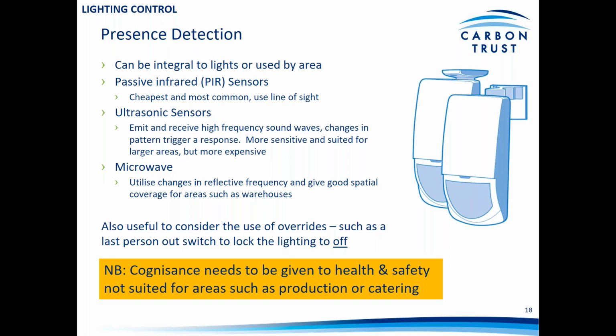So looking here at presence detection, this can be integral to the luminaires themselves. So you quite often will see this built into panels, built into lighting systems directly. So individual lights can switch off or dim as required based on presence detection, or often you'll get passive infrared sensors, as we see on the right, controlling a room or an area of a building.